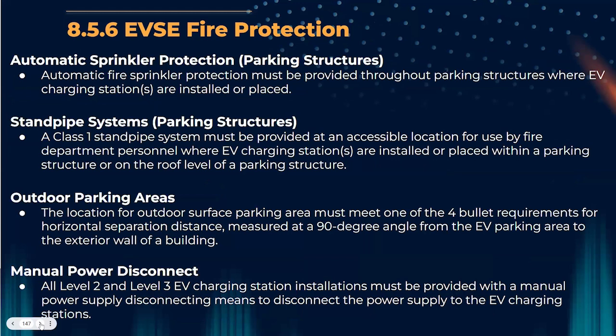Then there's manual power disconnects required for all level 2 and level 3 chargers. They should be located such that first responders can isolate the chargers in the event of an emergency. You don't want to put them right next to the chargers. You want to put them some distance away, so when the fire department comes in, they pass this emergency power off button, and then they can go to the chargers to get access after that.